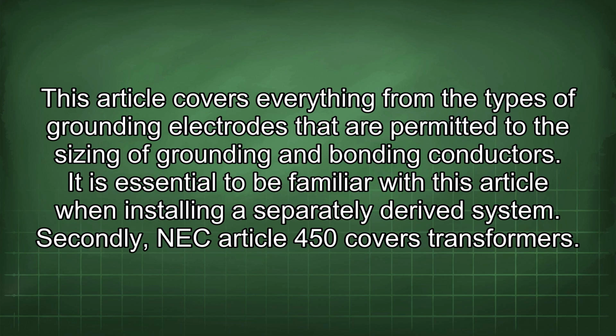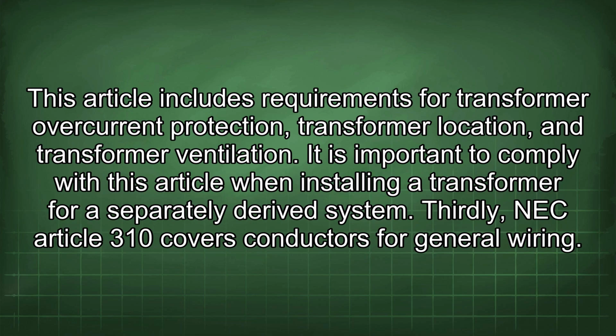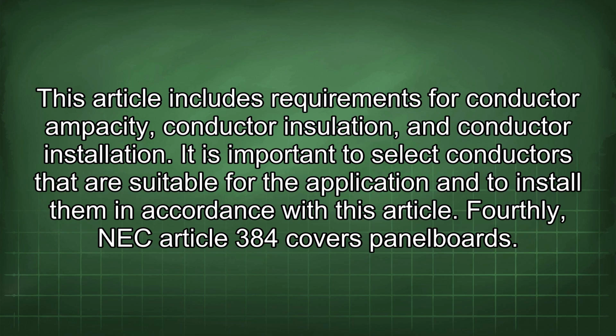Secondly, NEC Article 450 covers transformers. This article includes requirements for transformer overcurrent protection, transformer location, and transformer ventilation. It is important to comply with this article when installing a transformer for a separately derived system. Thirdly, NEC Article 310 covers conductors for general wiring. This article includes requirements for conductor ampacity, conductor insulation, and conductor installation. It is important to select conductors that are suitable for the application and to install them in accordance with this article.